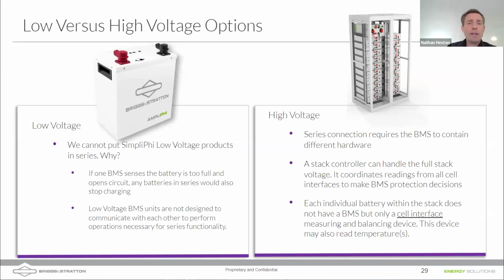The health of the battery does involve getting it to 100%, or 99% state of charge, occasionally. You do that by following the programming parameters, whether you're using an analog BMS or a communicating BMS like the AmpliPHI battery, which will automatically send these programming settings to compatible equipment.